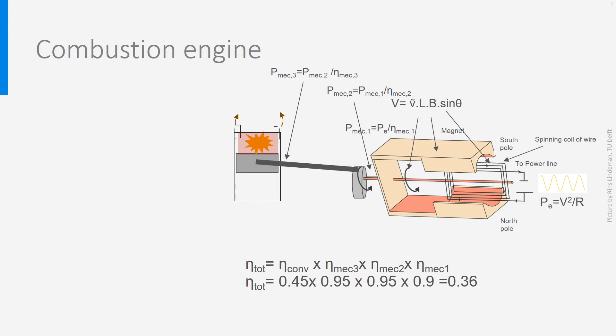In the combustion chamber itself, we have seen that 45% of the higher heating value is converted to piston energy. What happens with the remaining part? Well, around 30% is lost through the hot exhaust gases and the rest heats the cylinder itself, that must be cooled down. Typical temperatures in the combustion chamber are around 2500-3000 degrees Celsius, depending on the specific fuel. And this must be reduced strongly to 150 to 200 degrees to not damage the lubricating oil and equipment.